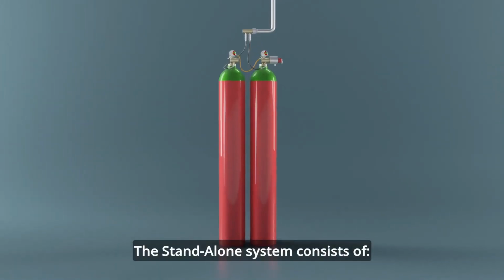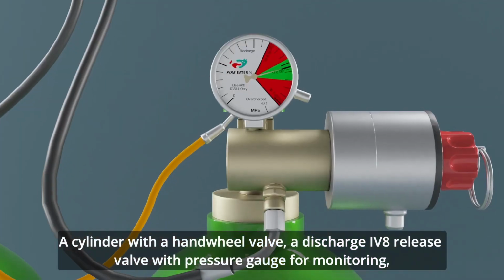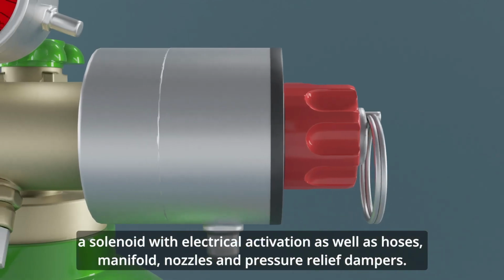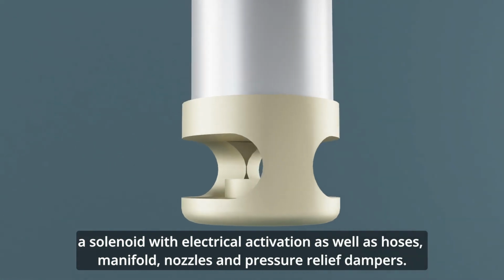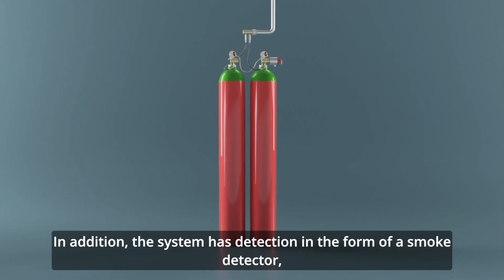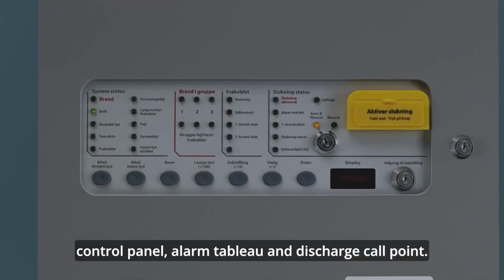The standalone system consists of a cylinder with a hand wheel valve, a discharge IV8 release valve with pressure gauge for monitoring, a solenoid with electrical activation, as well as hoses, manifold, nozzles, and pressure relief dampers.